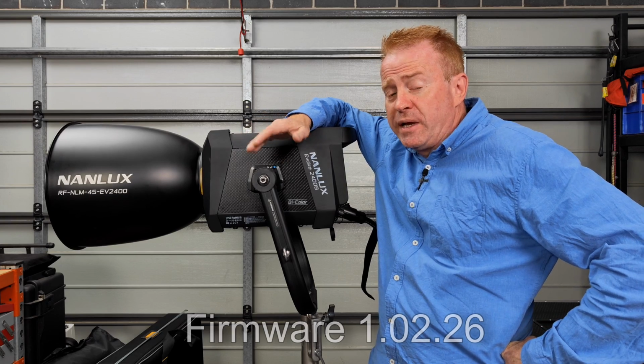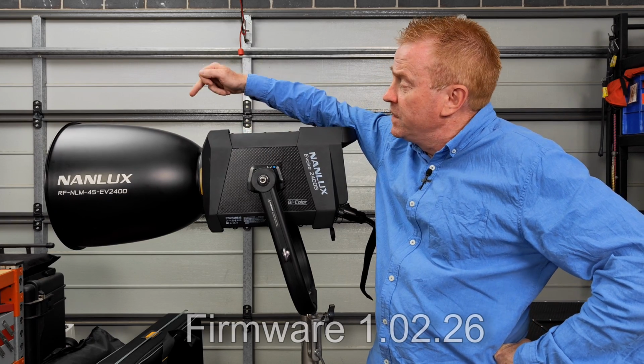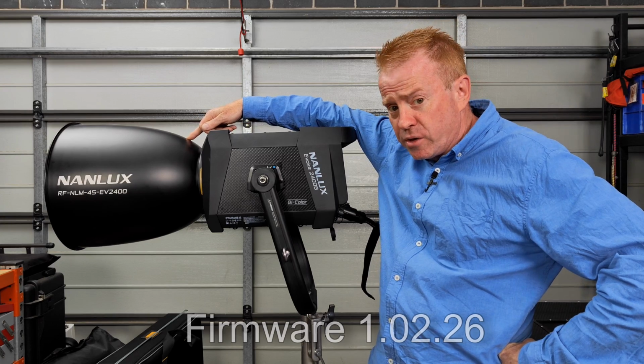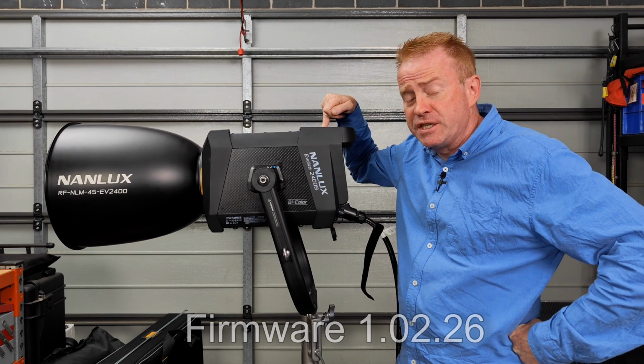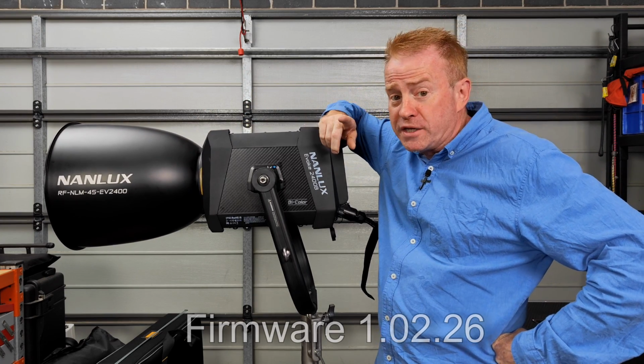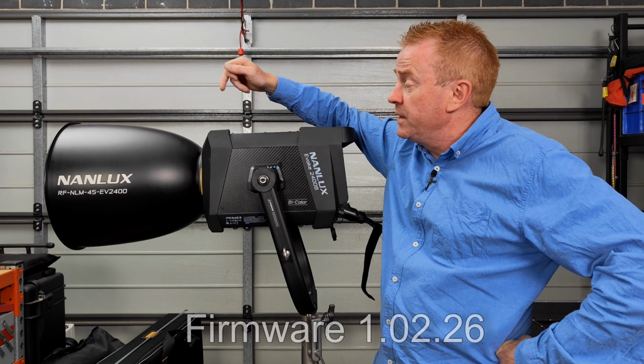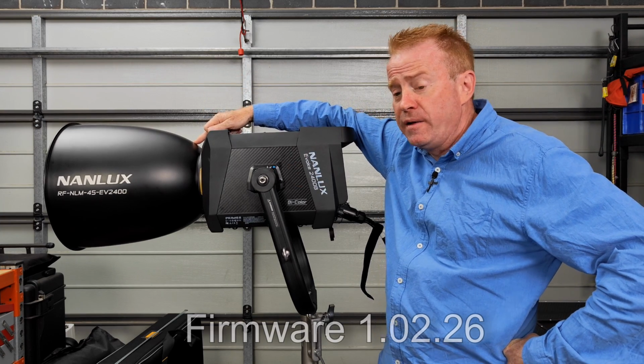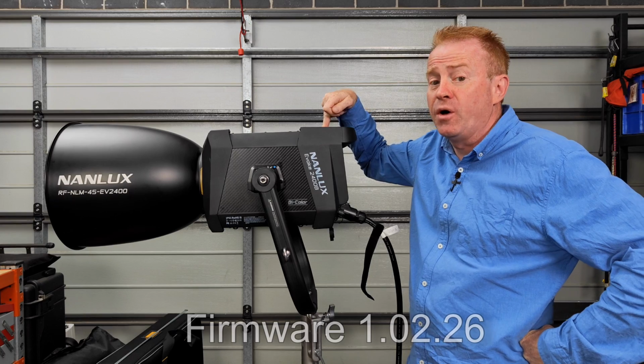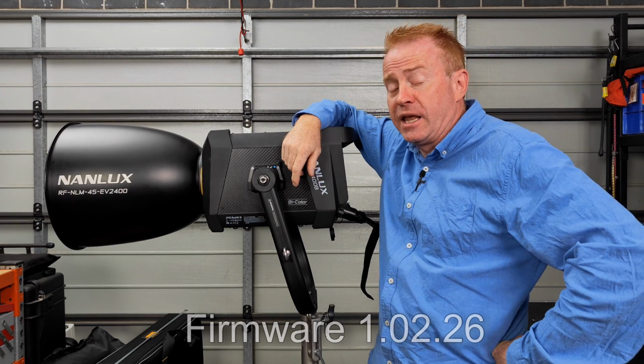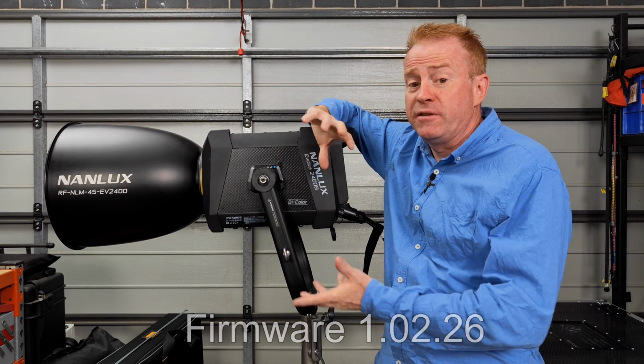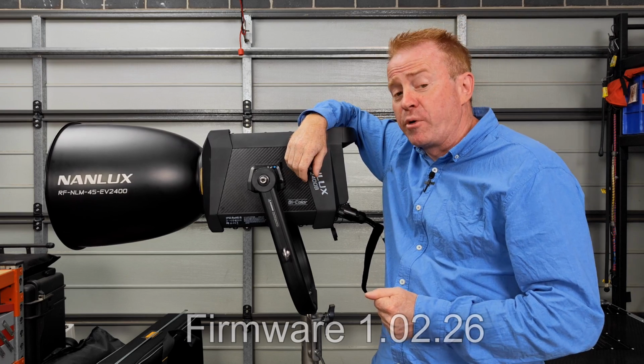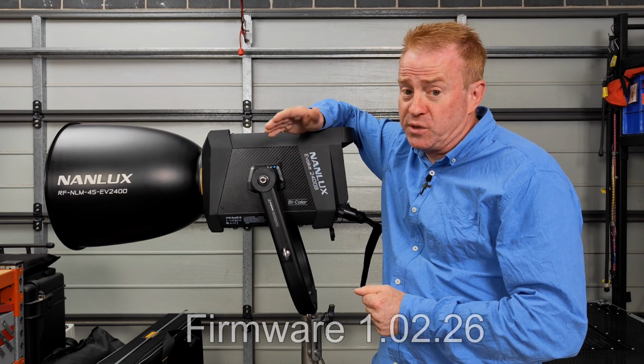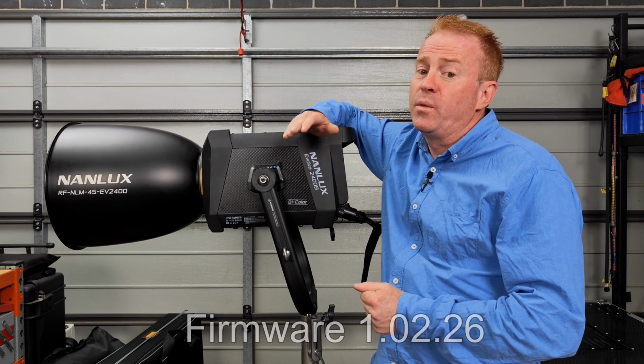So in case you're not following, let me break it down a little bit more. If you've got the 45-degree dish on the front and you've got the recognition system turned on, then you are not getting calibrated light output. If you've got the 45-degree dish on and you've got the recognition system turned off, then you are getting the calibrated light output. Essentially, they've got the programming backwards. The calibrated light output is turned off when it should be turned on, and it's turned on when it should be turned off.